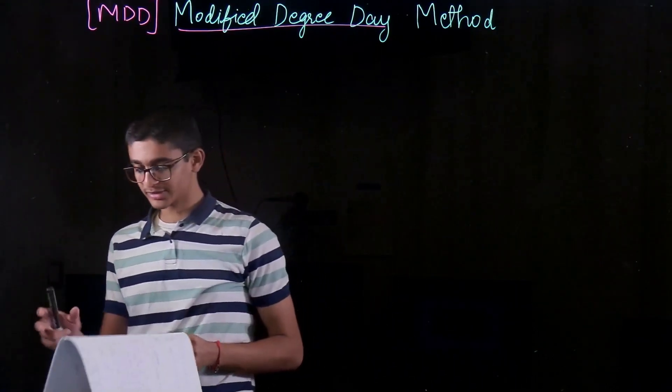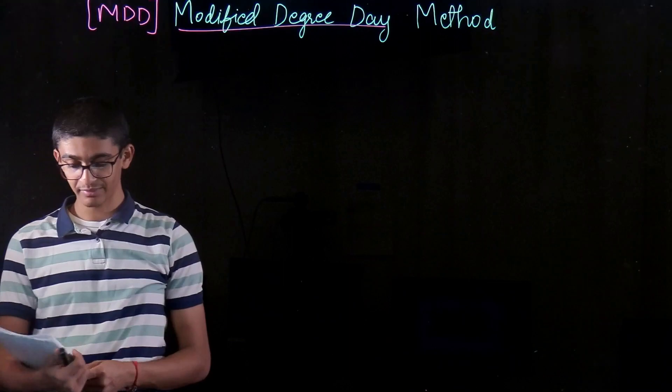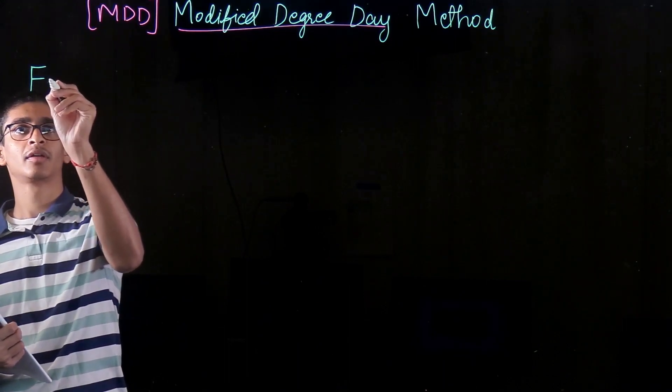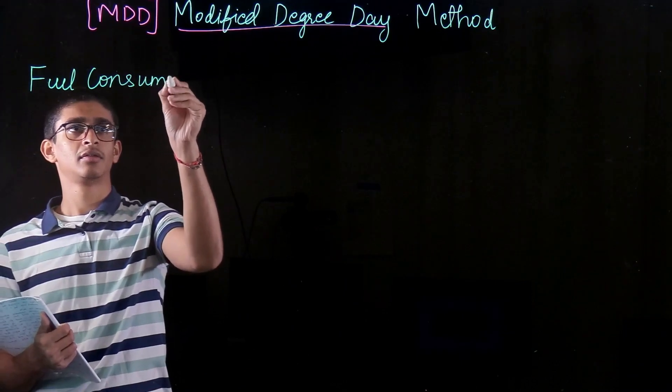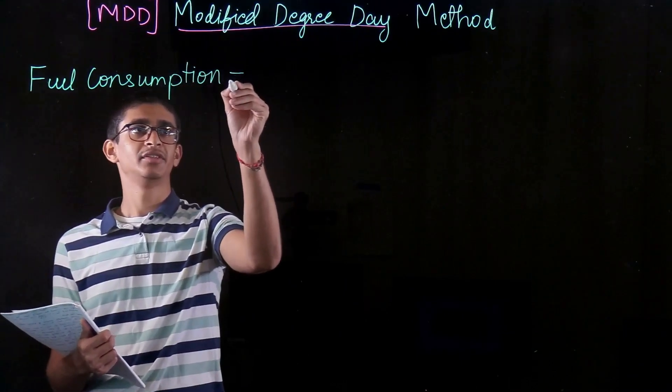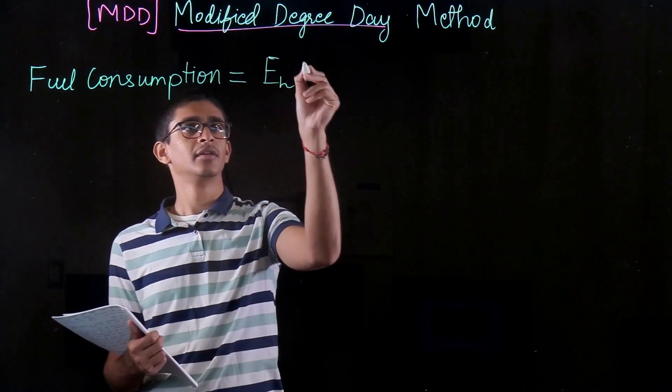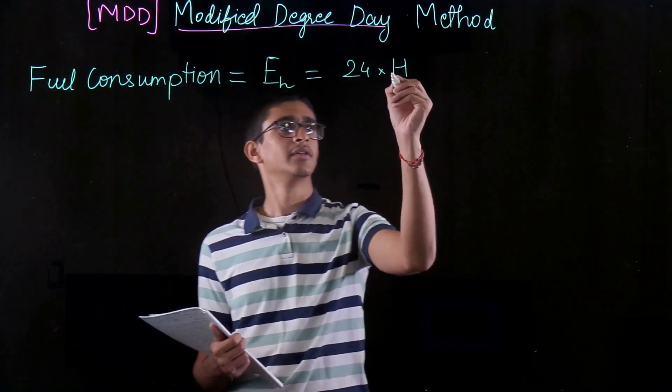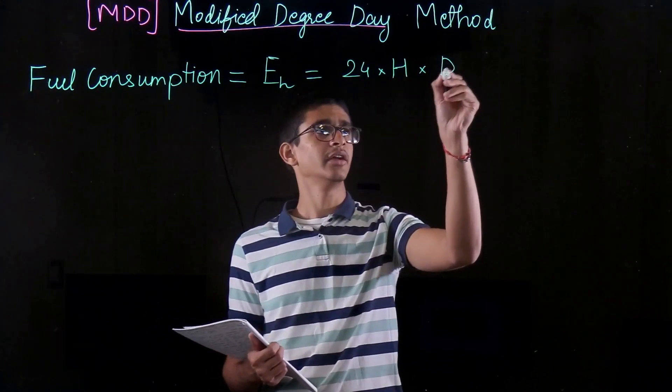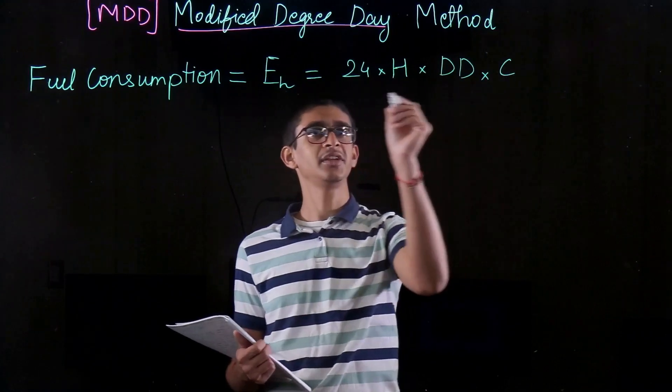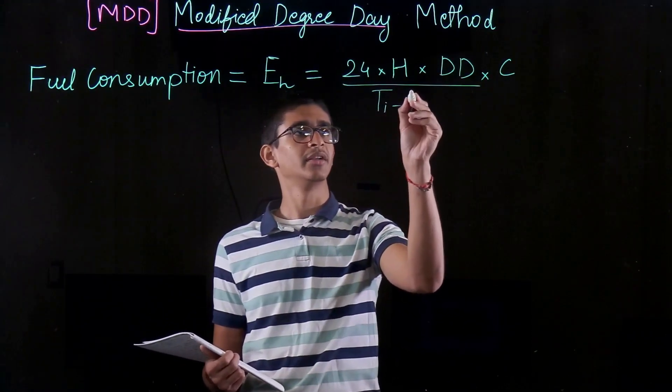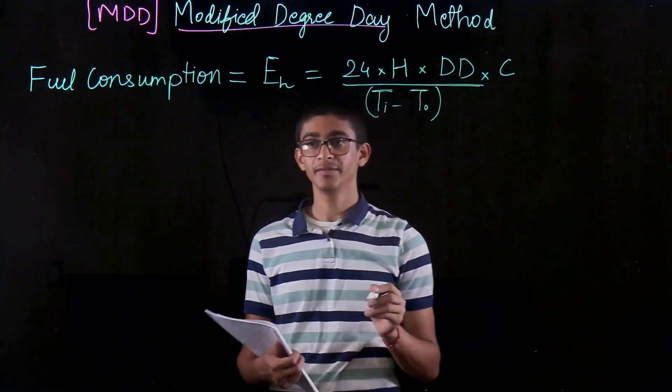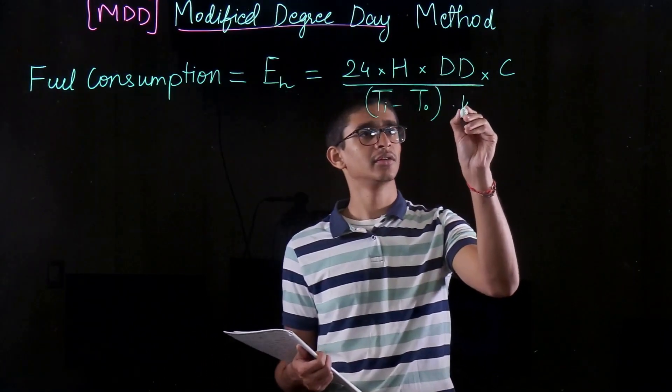The formula for the fuel consumption based on the modified degree day method is very much similar to what we had previously for degree day method. And this gives the fuel consumption which is equal to EH, and it is given by 24 into H times degree day into some factor of C divided by TI minus T out, into K into V.